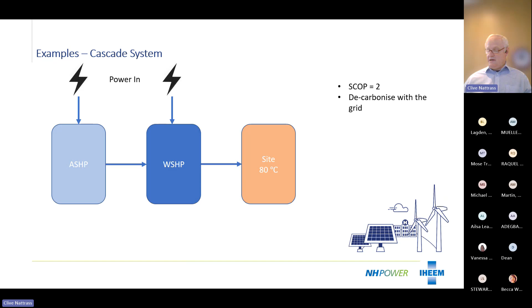The problem with that is you've got to power both heat pumps, and you might get a seasonal coefficient of performance - because you want to know what it's like over the year - of, say, 2, which means you put in 1 unit of electricity and get 2 units of heat out of it. It'll work, give you the temperatures, and decarbonize with the grid. The main issue will be the cost of running it - that's probably the major focus here.